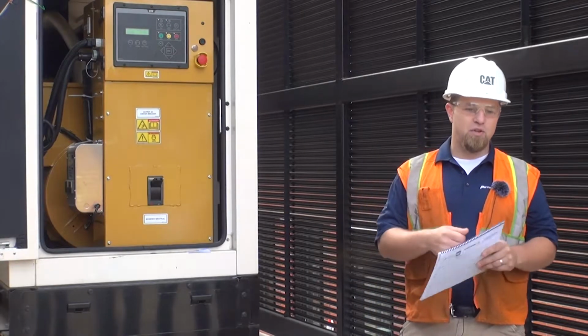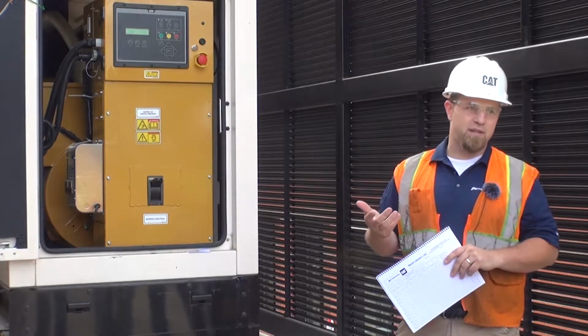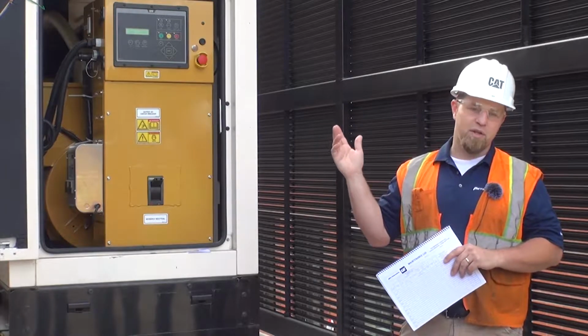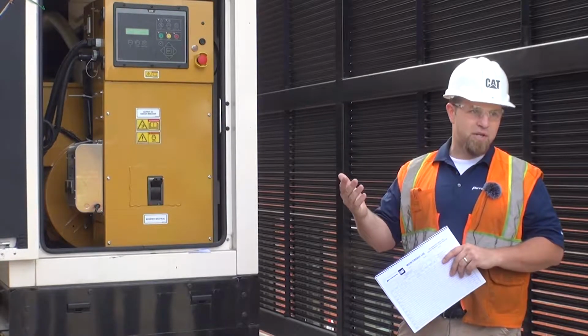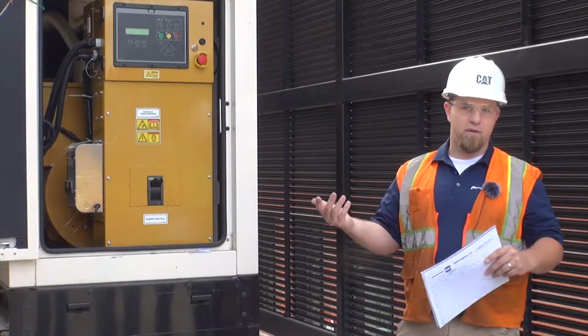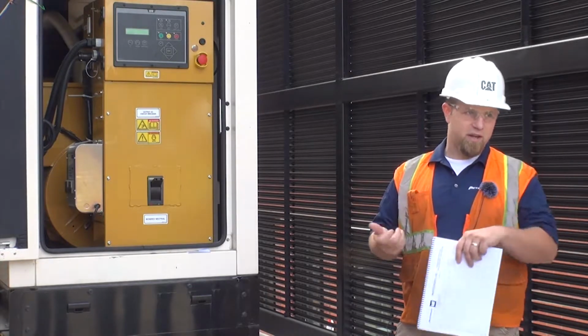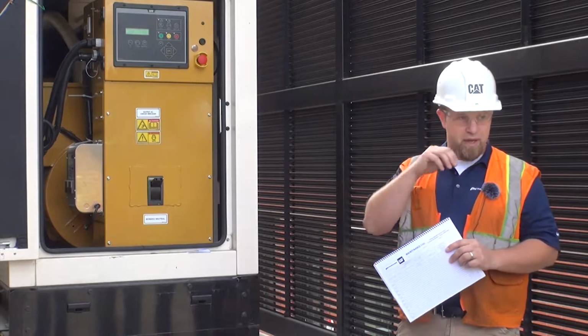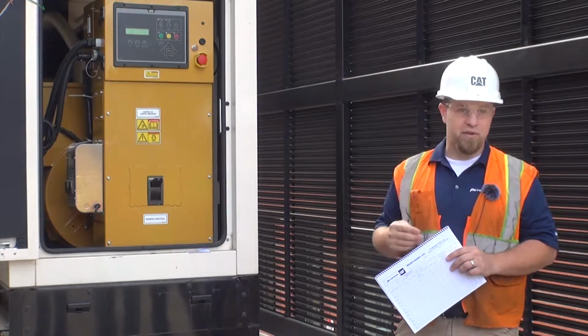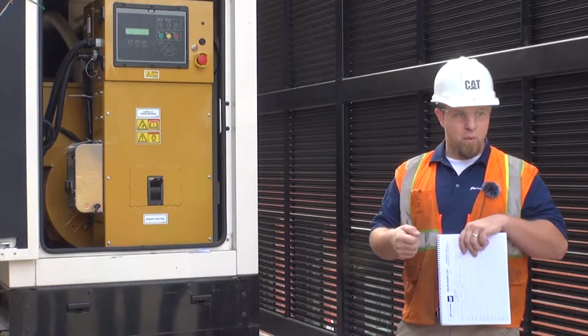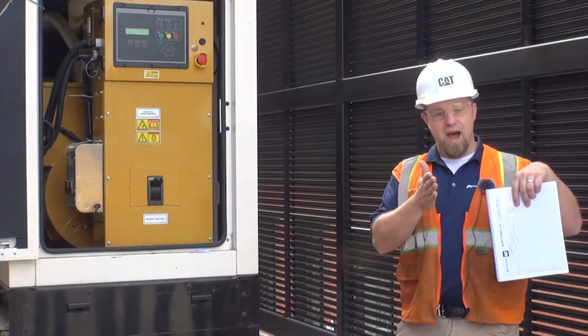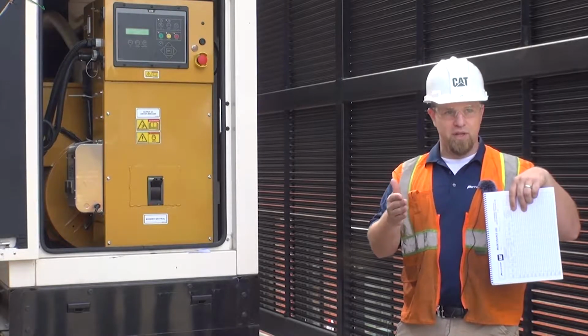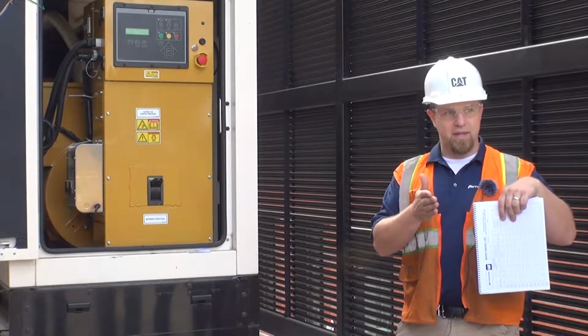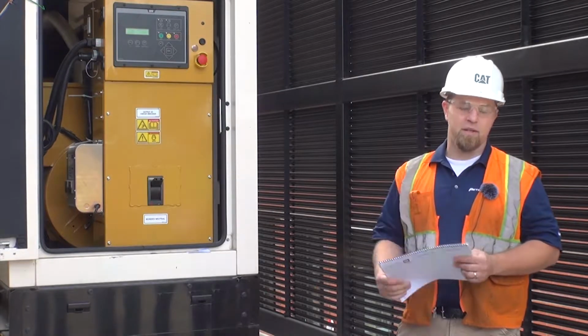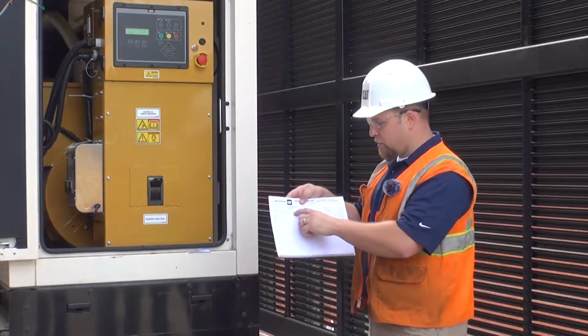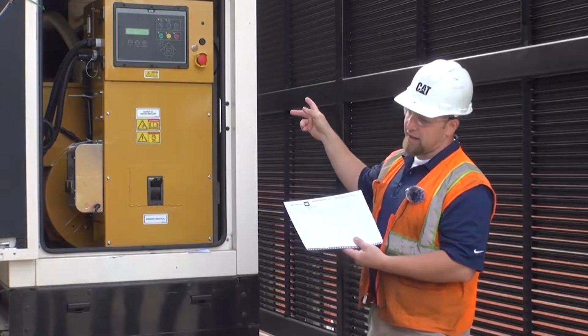So the only time you actually do wipe that is if you were to have a building power outage and it shut down on low oil pressure, which is a hard shutdown. Then obviously you would be going over there and need to wipe it, check it, and put it back in, top off the oil if that were the case, and get yourself back up and running. Other than that, it always should be cold, and just not wiping it off, checking where it's at, always at the high end. Never want to have it in the in-between or on the low side. We always just go with the high end of the stick. So full mark right at it. Going down the line on here, coolant, we'll show you where you can check that. It's up top.